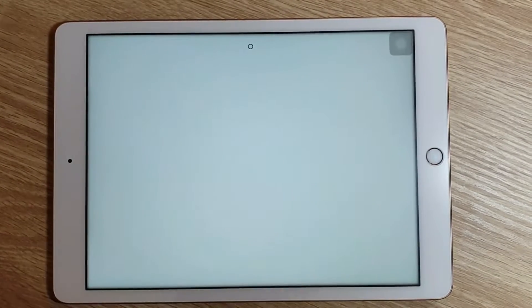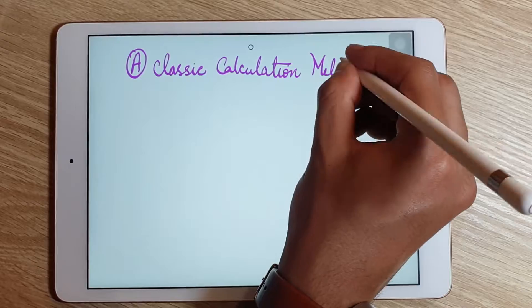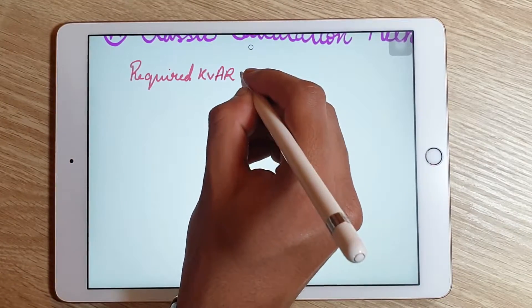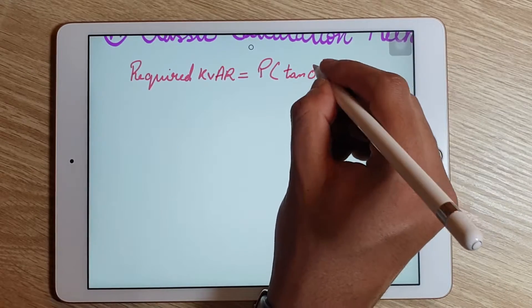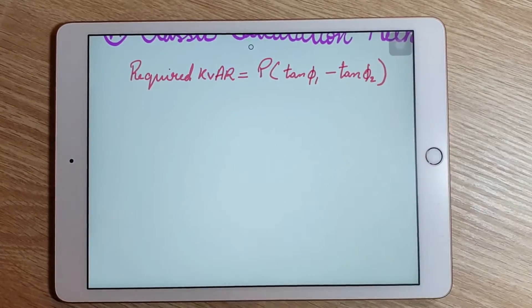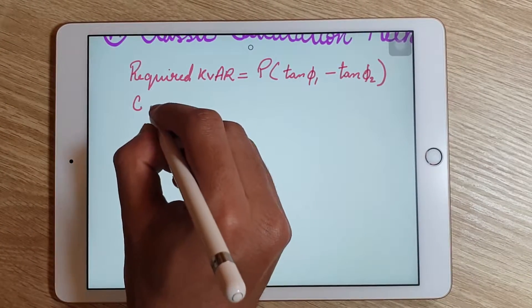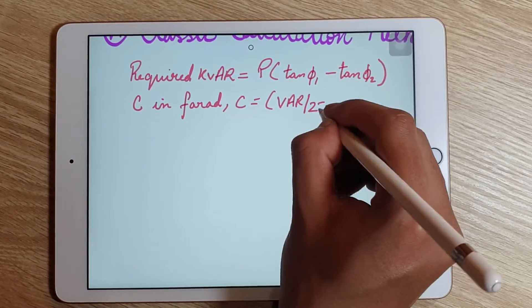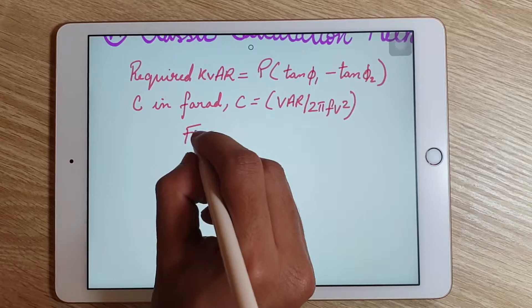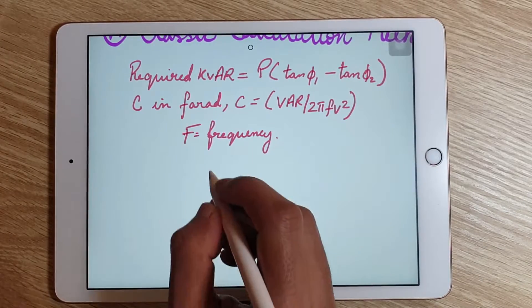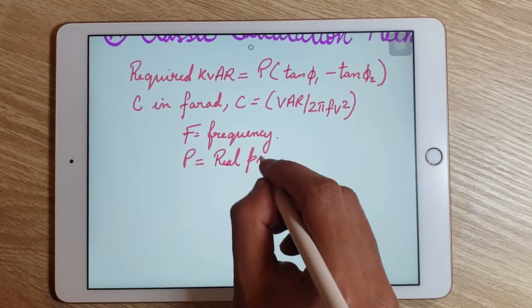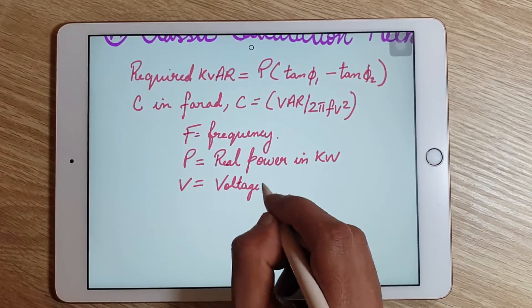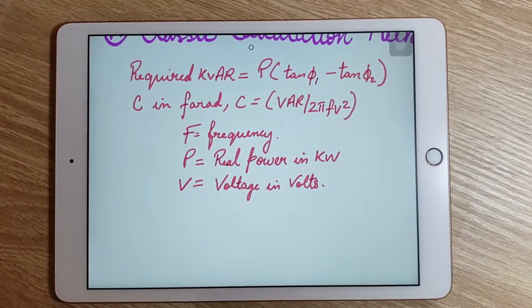Let's focus on the first method, which is the classical calculation method. The formula to calculate the required KVAR is: required KVAR = P × (tan θ1 − tan θ2). The capacitance C in Farads is given by C = VAR / (2πFV²), where F is frequency in Hertz, P is real power in kilowatts, and V is the voltage of the power system in volts.